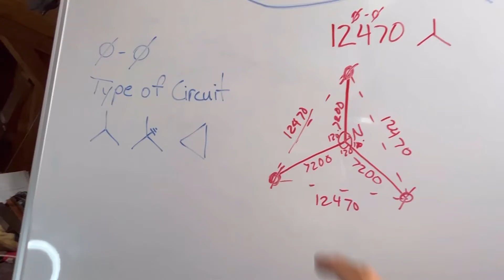So in a Y circuit, I have two different voltages that I can work with. I've got both a phase-to-phase voltage, obviously, which in this case is 12,470 volts. And I've got a phase-to-neutral voltage, which in this case is 7,200 volts. So in a Y circuit, I've got two different voltages I have to work with. Phase to phase, 12,470 volts. Phase to neutral, 7,200 volts.